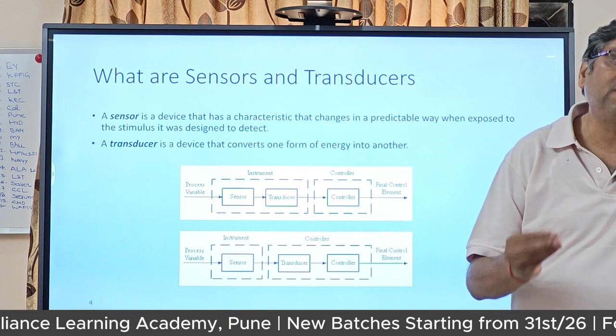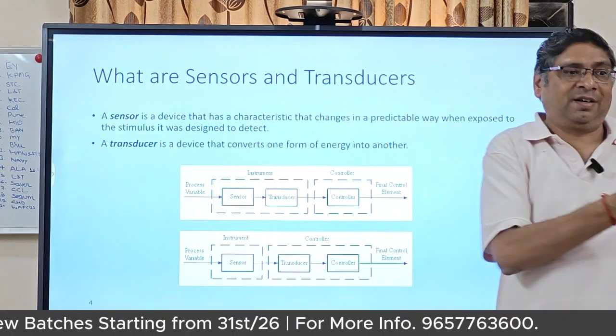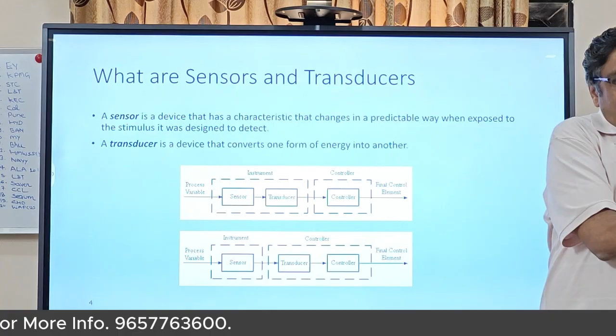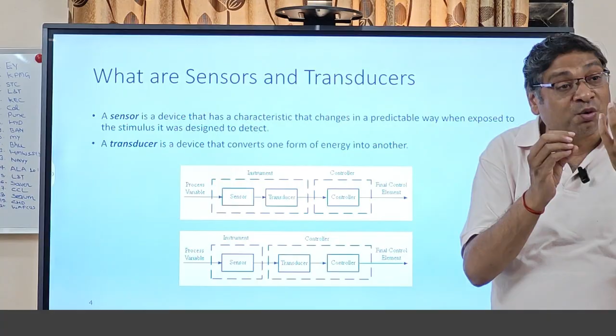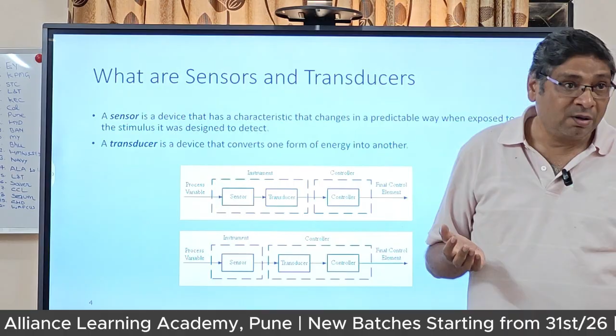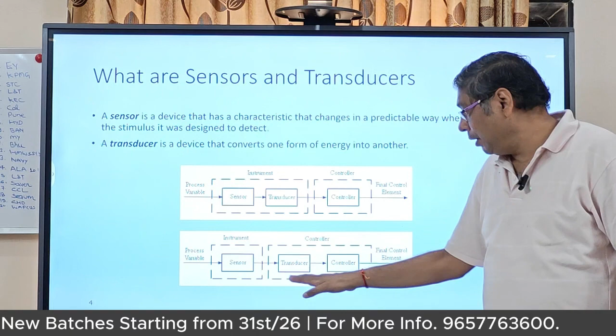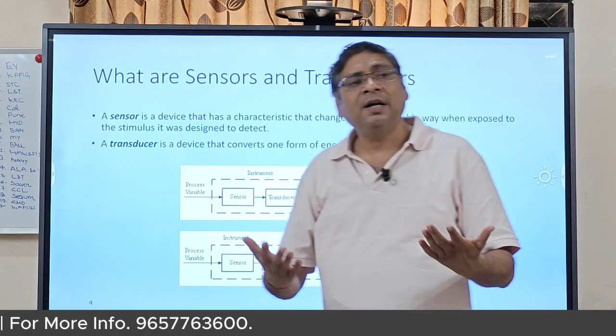Display can be our sensor, smart sensors can be, but if you talk about conventional, then everything is different. Sensor is different, transducer is different, and display is different. One more word is signal conditioning - normally the transducer does that signal conditioning, because it depends on the requirement: you want a current output, 4-20 output, Ethernet output, or pulse output. So sometimes your sensor is different, but transducer and controller are same, and if it's a controller, it can be a display also.